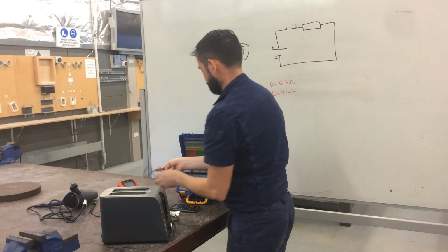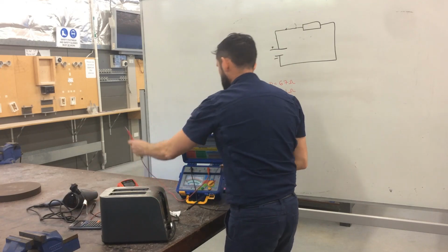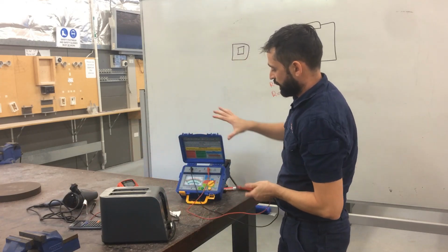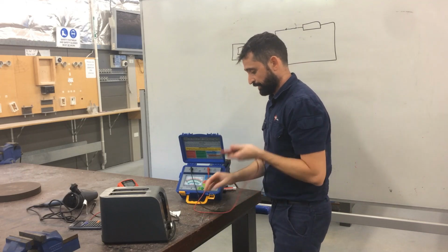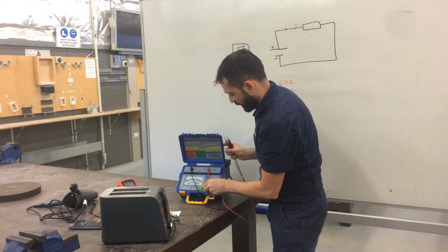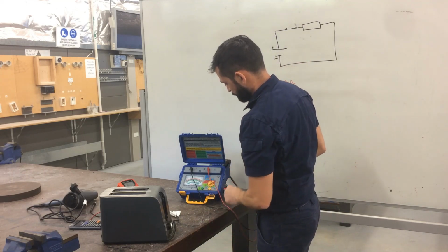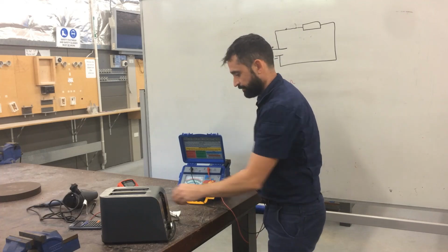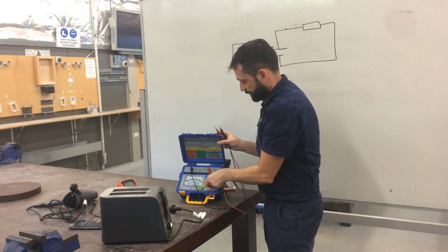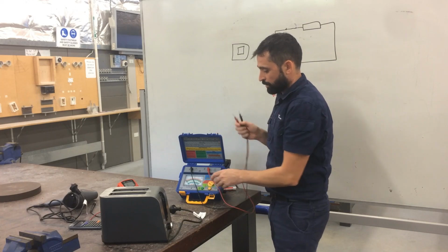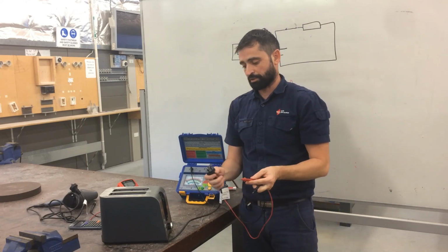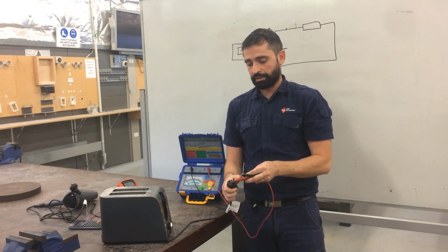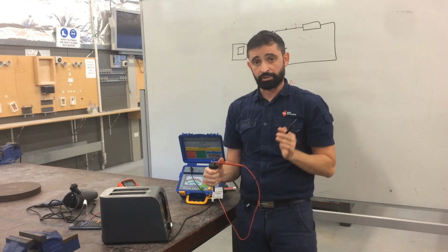Insulation resistance test. Okay. Now this has already been checked for calibration previously. But we will do a battery check again before we use it. Okay, battery's good. Take it off. Now what we do is we're going to set this to 500 volts. So all we're doing is we're going to check our active conductors down to earth. We want to make sure that the current is going to go where it's supposed to go.